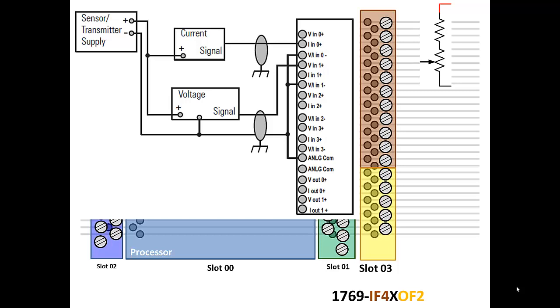You could add an additional 10 volt power supply, but in this case we're just going to use a voltage divider. We cannot meter 0 to 24 volts DC into our analog input, so we need to drop 14 of the 24 volts to provide the correct range. This is done with a very inexpensive carbon resistor in series with the potentiometer as seen here. That dropping resistor above the pot has a resistance of 140% of that of the pot, or 1.4 times the resistance of the pot. If the pot is a 100k, then you need a 140k dropping resistor. That ratio 140k and 100k, that's a total of 240k across 24 volts, that gives you 10 volts across the 100k for the potentiometer.